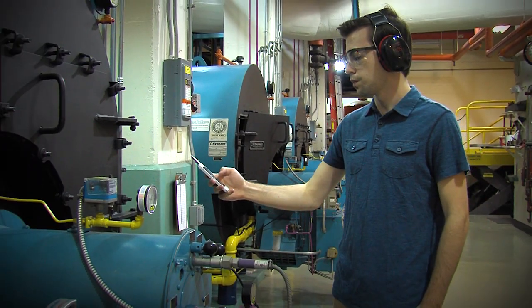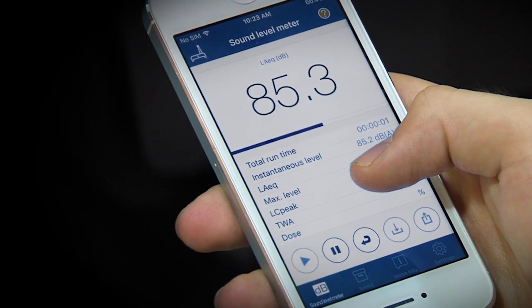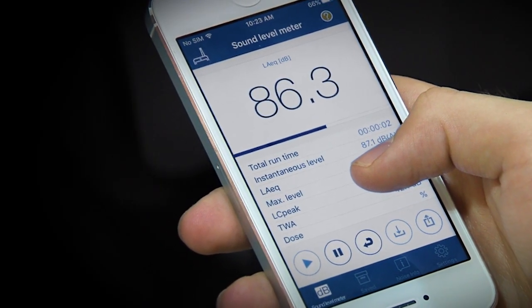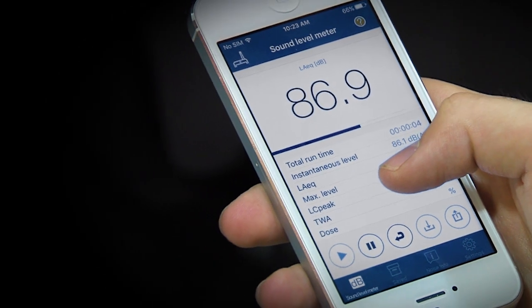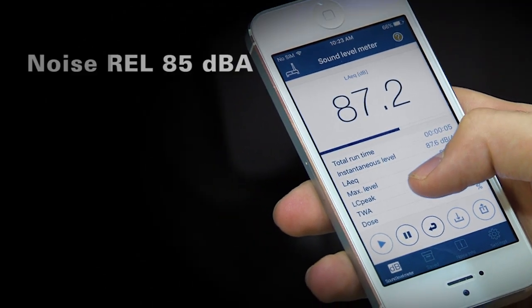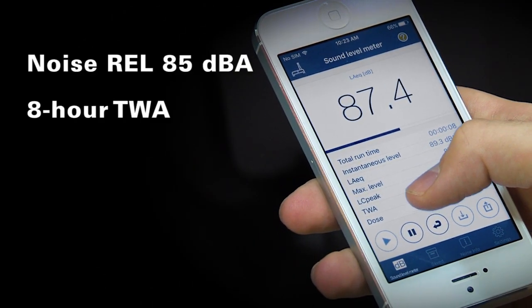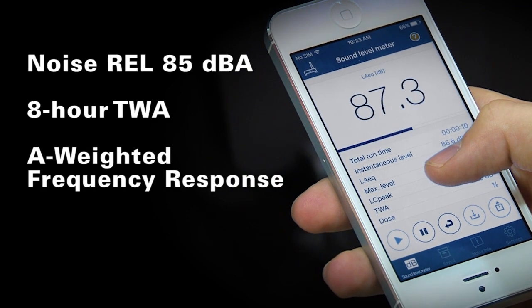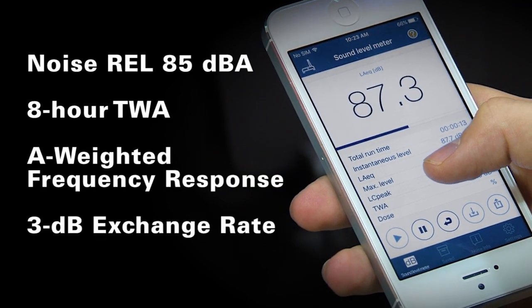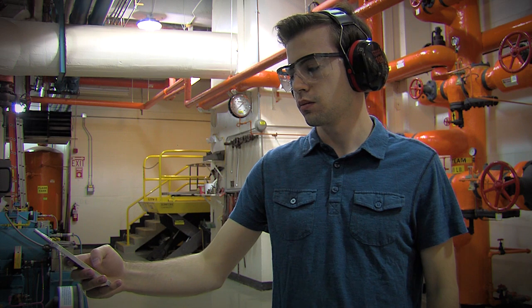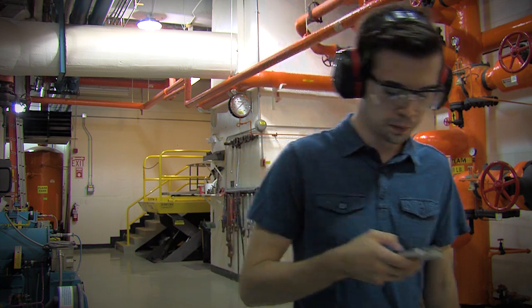NIOSH has established recommended exposure limits, or RELs, for various hazards on the basis of the best available science and practice. The REL for noise is 85 decibels as an 8-hour time-weighted average using the A-weighting frequency response and a 3-decibel exchange rate. Exposures at or above this level are considered hazardous.